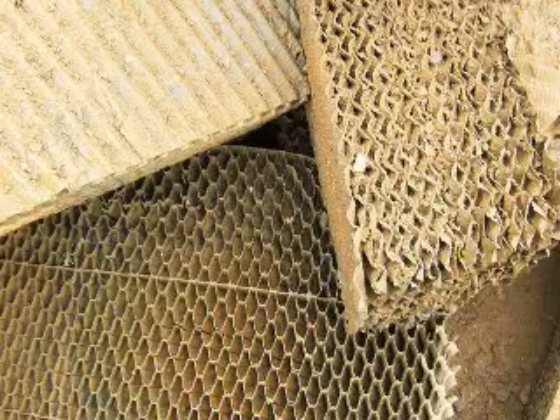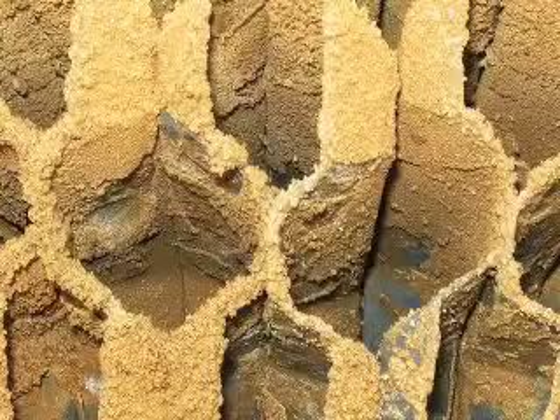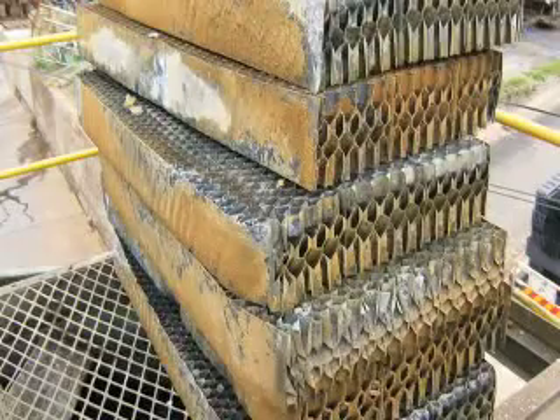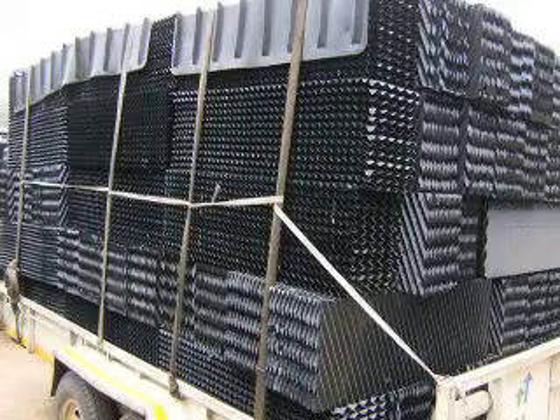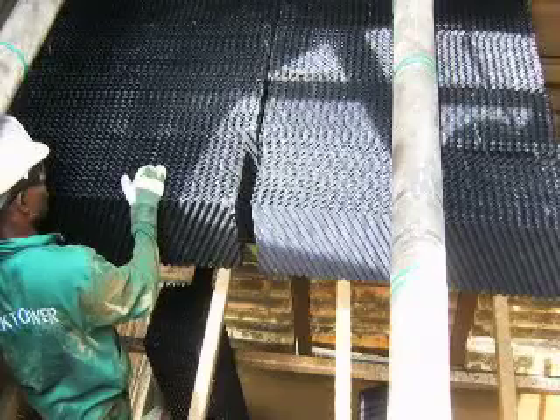We had a set pattern to replace the packings on a cooling tower every 2 years, but at this stage it looks as if we'll be able to stretch it for a longer period, if not indefinitely, until the packing fails due to normal wear and tear, but not due to scaling of the packing.